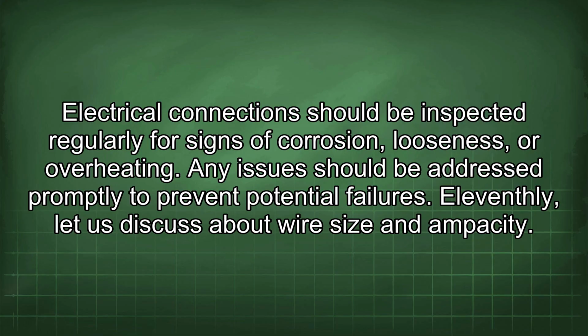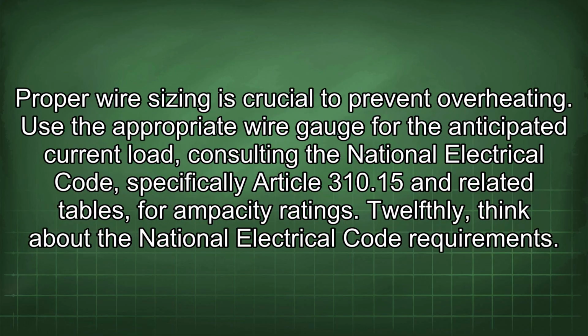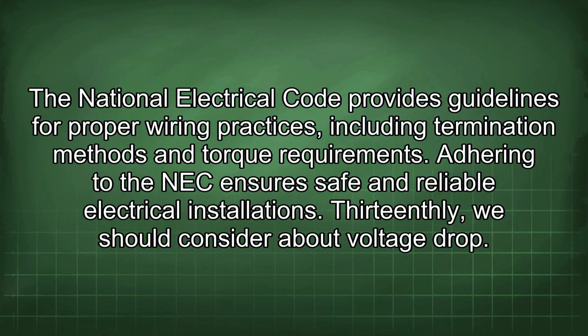11thly, let us discuss wire size and ampacity. Proper wire sizing is crucial to prevent overheating. Use the appropriate wire gauge for the anticipated current load, consulting the National Electrical Code, specifically Article 310.15 and related tables for ampacity ratings. 12thly, think about the National Electrical Code requirements. The National Electrical Code provides guidelines for proper wiring practices, including termination methods and torque requirements. Adhering to the NEC ensures safe and reliable electrical installations.